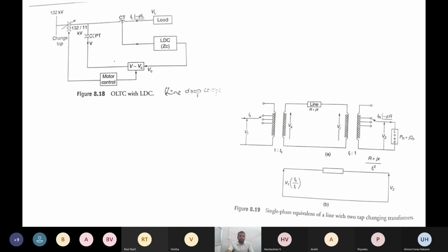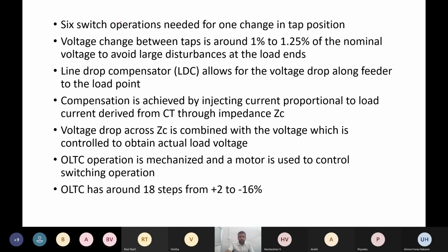So as I told, now the actual voltage V and the voltage that is observed through the ZC, that difference. So the CT will be there, the PT will be there. So from there we can actually measure our actual current and actual voltages. So by measuring this point, so this line drop compensator.